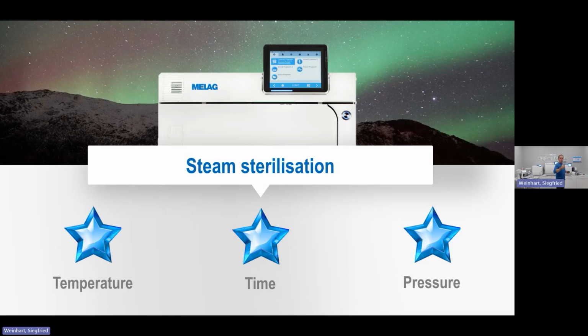They're incredibly good, so we do rely on those temperatures. Most traditional sterilisers will look at a 3-minute sterilisation holding time, which is the EN norm. However, most modern autoclaves do tend to extend that, so they look more towards the 5-minute mark, where it'll physically hold 134 to 137 degrees, and we see it hit around 135, 135 and a half. EN 13060 is the EN norm that looks after all of these units you can see here, which are called benchtop sterilisers. All manufacturers have to make their equipment to the standards within it.